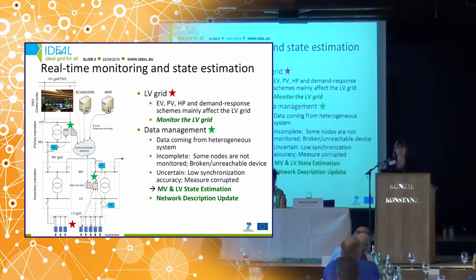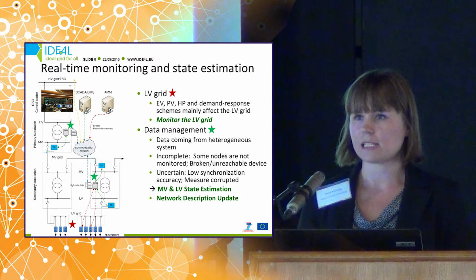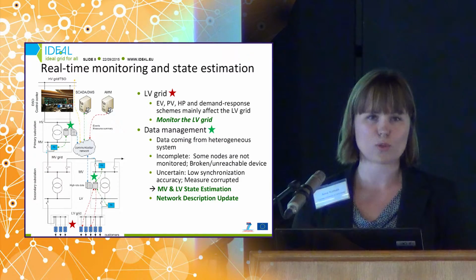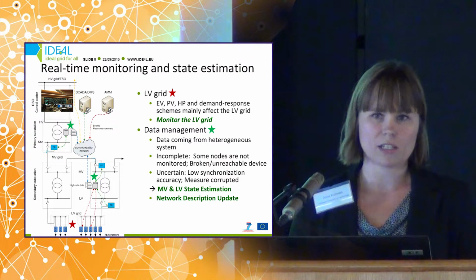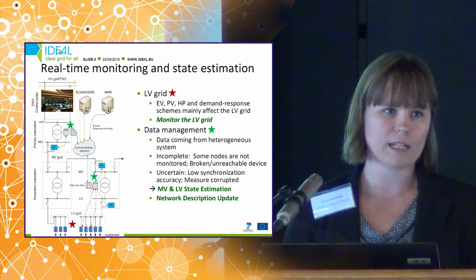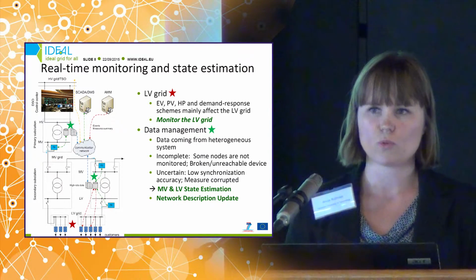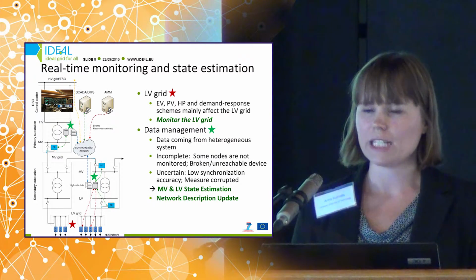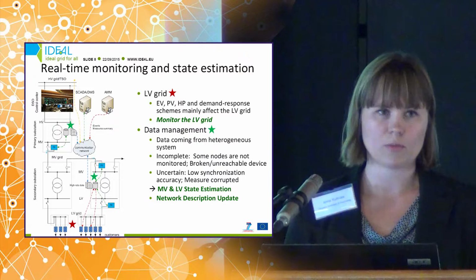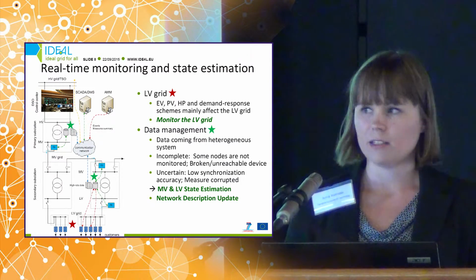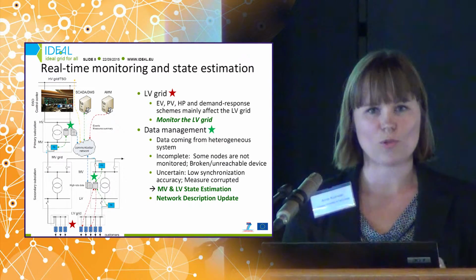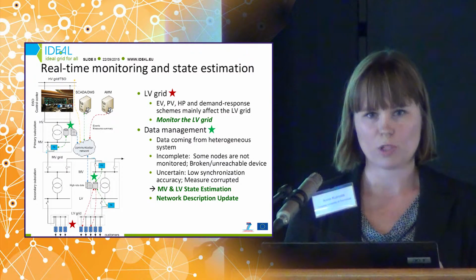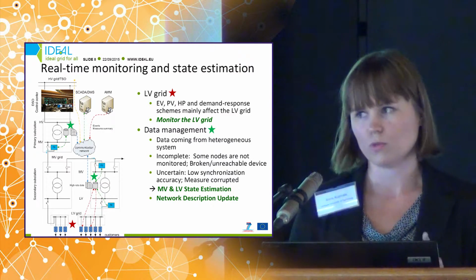Only the necessary data is transferred to the primary substation automation unit, and in this state estimation use case, the necessary data is only the sum of real and reactive power transfers through the distribution transformer. So the needed data transfer is much smaller than if we would transfer all the smart meter data to the primary substation automation unit or to the control center level.